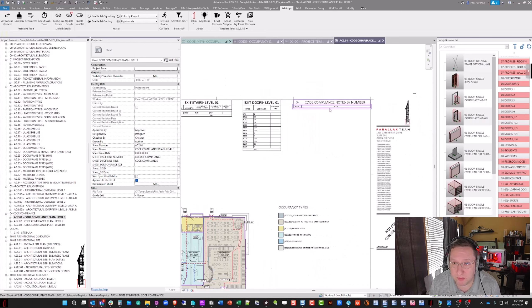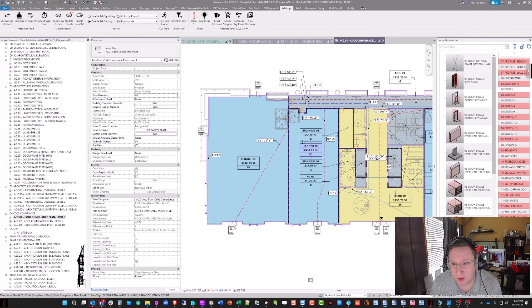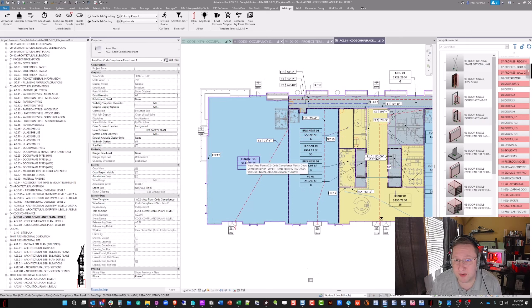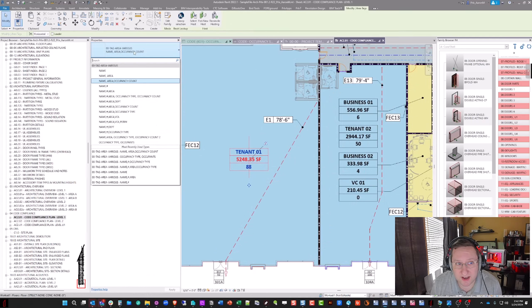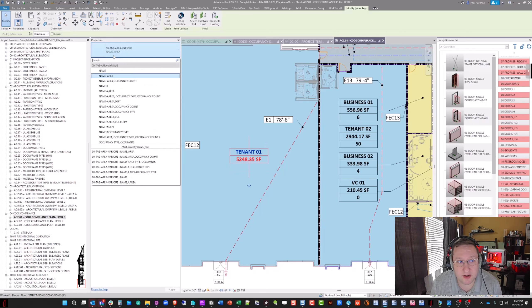To start, when we first look at the code compliance plan, it is an area plan. In our version of the template, we have the areas colored by occupancy type — that's not required, it's just something we do so we can graphically check which areas are coded with which occupancy type. Our life safety or code compliance plan has a number of schedules that run across the top of the sheet, sometimes moved to the side depending on the building plan. We have one schedule listing the lengths of all travel distance paths per level, and one table calculating the total square footage, the area per occupant, and the number of people on this level of the building.